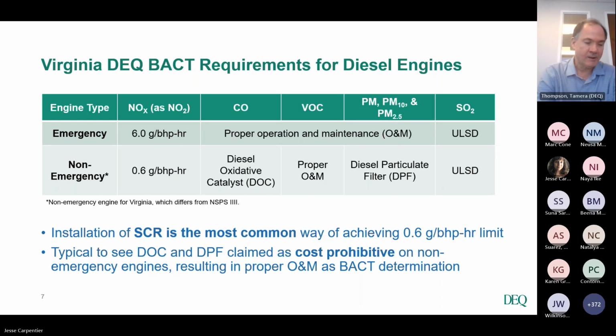I'll also say we sometimes deviate, but we have really stuck with that 6.0 number for emergency units at data centers, particularly in the Northern Virginia non-attainment area. Some engine manufacturers and applicants have made arguments trying to get us to raise that number based on vendor data, but through a great deal of source testing, we have found that folks can meet this standard if they set their units and engines up correctly. So we do not deviate from that 6.0 very often, or really at all, as far as I know.